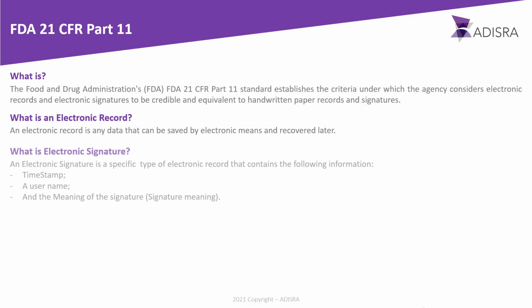What is an electronic signature? An electronic signature is a specific type of electronic record that contains the following information: timestamp, a username, and the meaning of the signature. Its main function is to distinguish the uniqueness of any user operating the SCADA system. The main objective is to guarantee the action's non-repudiation by a system user.